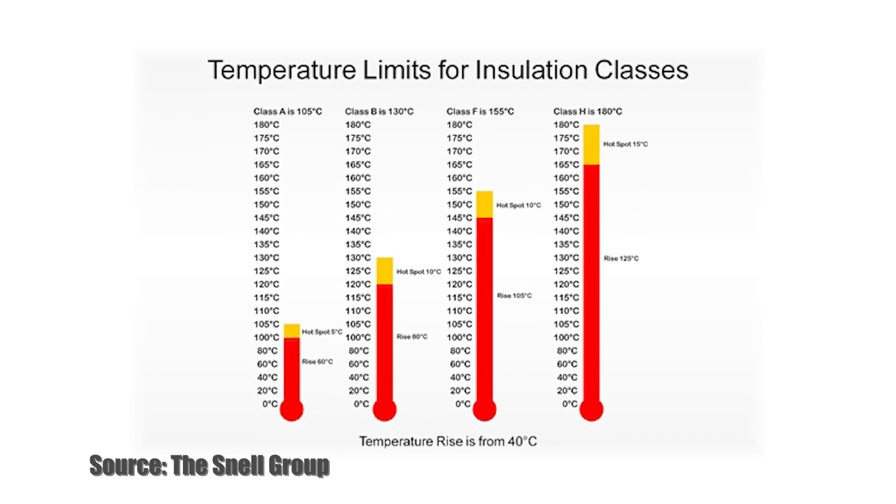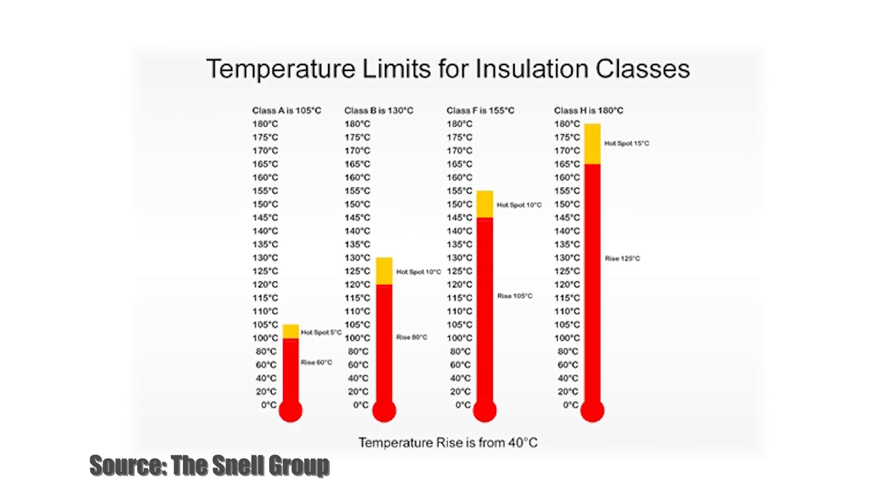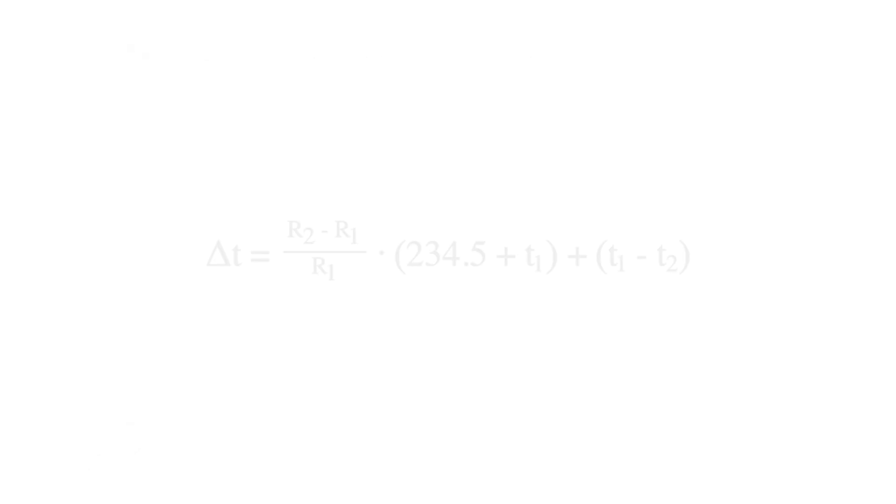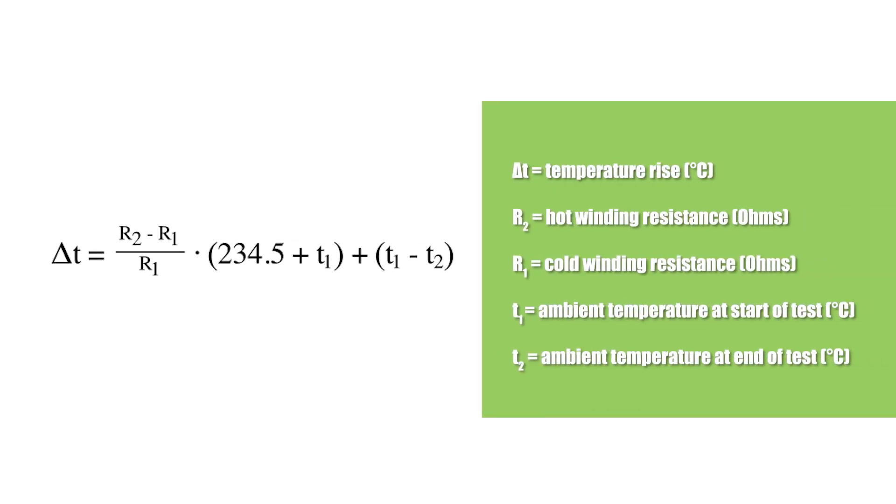However, adjustment tables and calculations are available to determine the reduced maximum operating temperature for conditions outside of those specified by the insulation class. Temperature rise is calculated based on the change in resistance of the windings, with a correction for any change in ambient temperature between the start and the end of the test.